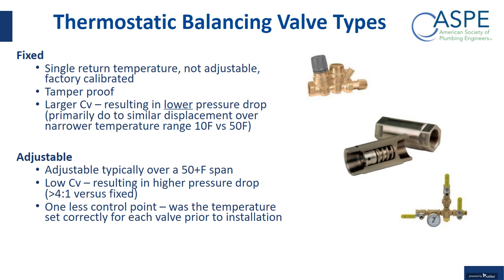The other thing with the adjustable is that because they are adjustable, you're depending on a human to put those temperatures where they need to be. So that's one less control point. If you have a building with 100 thermostatic balancing valves and you're having hot water issues, one of the questions you have with the adjustable that you don't have with the fixed is, were all of those set at the exact same setting, or were some set higher or lower than they should be? So it's one less control point you have in the system. Again, that flexibility comes with a price, and it's something you need to keep in mind.